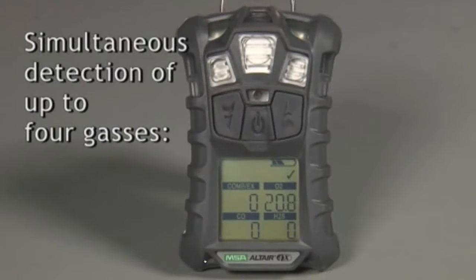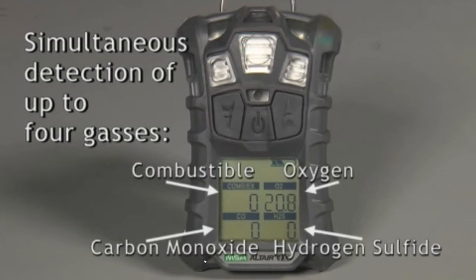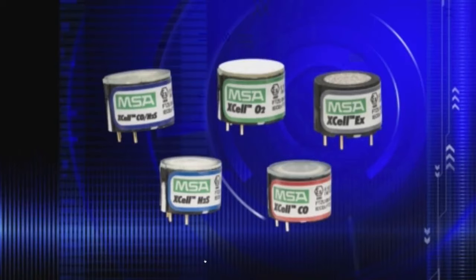The Altair 4X multi-gas detector can be used for simultaneous detection of up to 4 gases: combustible gases, oxygen, carbon monoxide, and hydrogen sulfide. MSA's XCell sensor technology is used to detect these gases. These sensors, with built-in microelectronics, provide extremely high performance levels when properly maintained. These sensors have a projected lifetime of over 4 years.